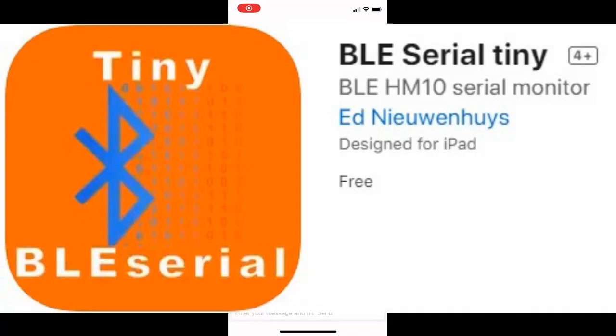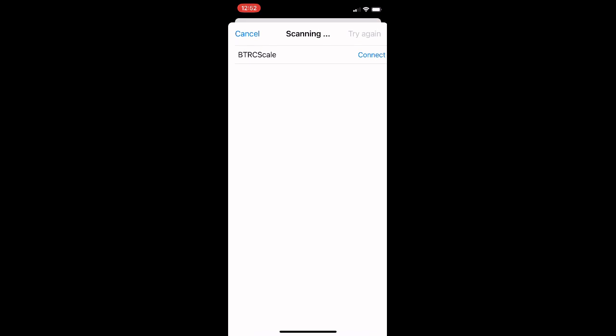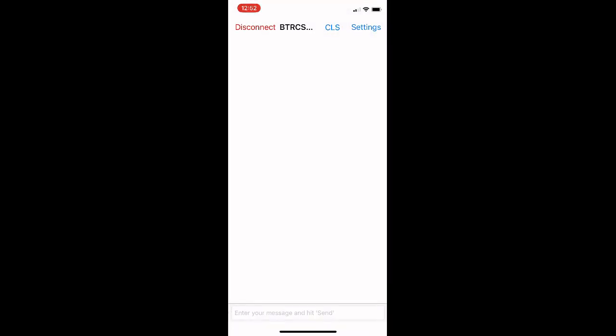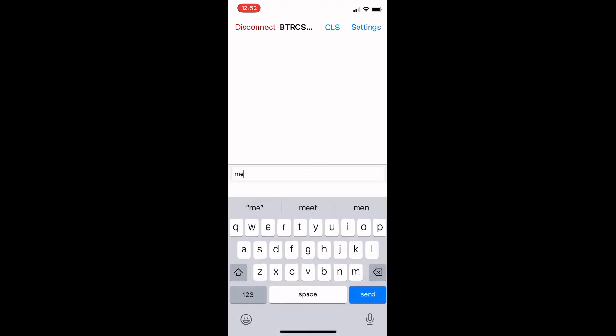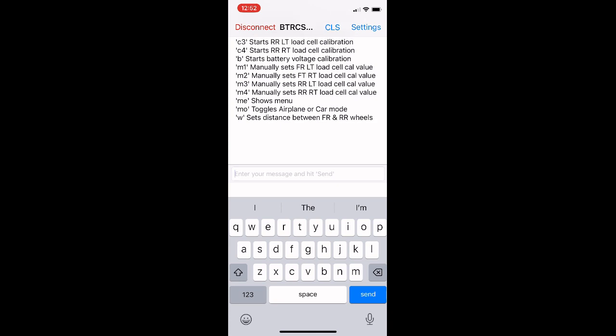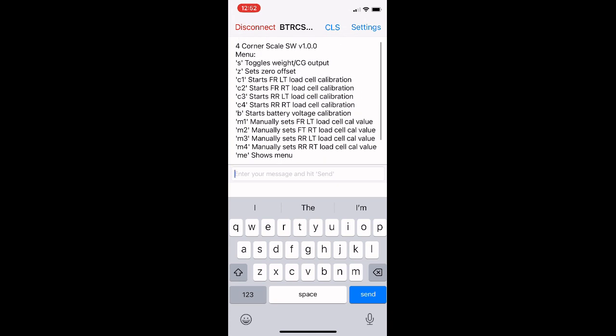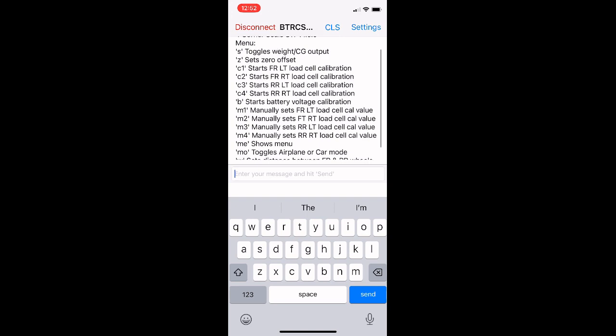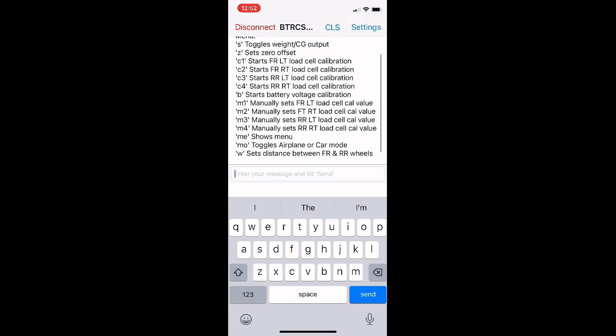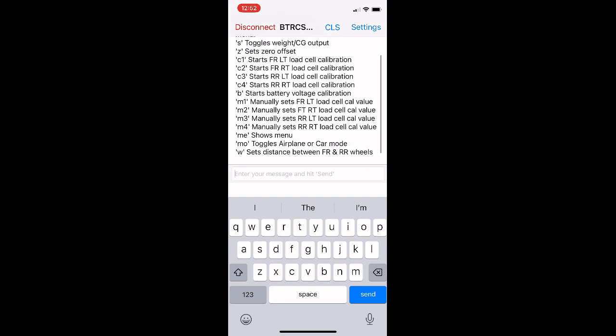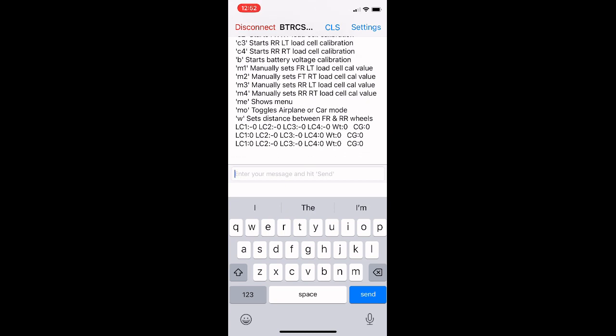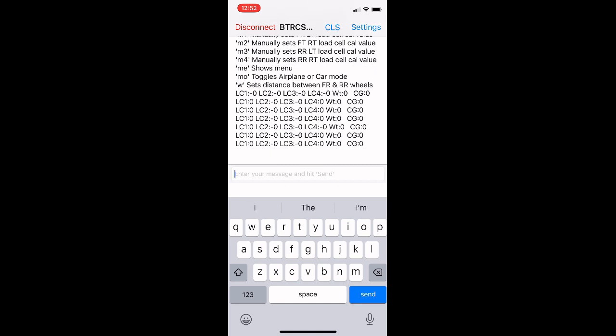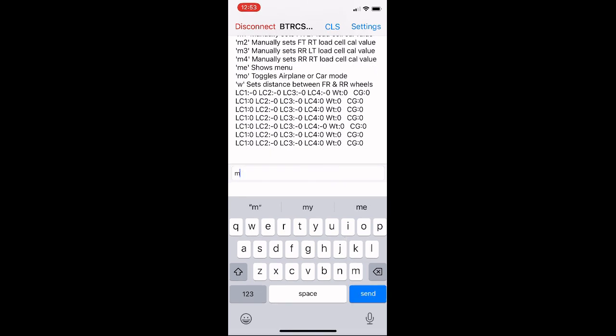Bluetooth app seems to be the best to emulate the COM port. Open the app, connect. If you type in ME, you can get the menu at any time. Z is for re-zeroing, C1 is to calibrate the one load cell, so on and so on. W is to set the distance between the wheel sets. If you type in S, it turns on the serial monitor where it just cranks out each load cell value. They're all reading 0 right now, but that's why it looks that way.